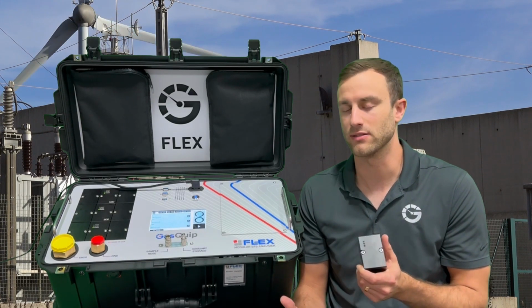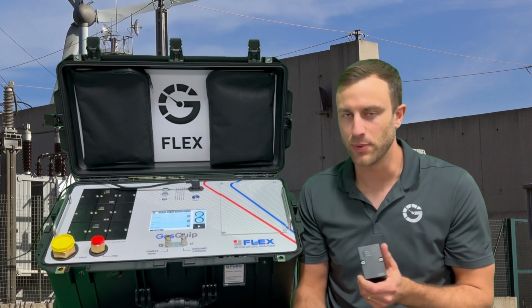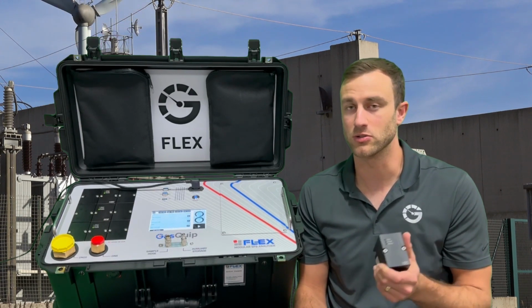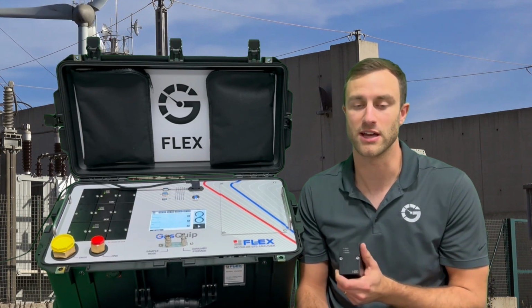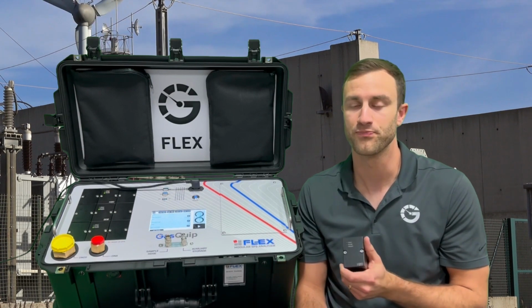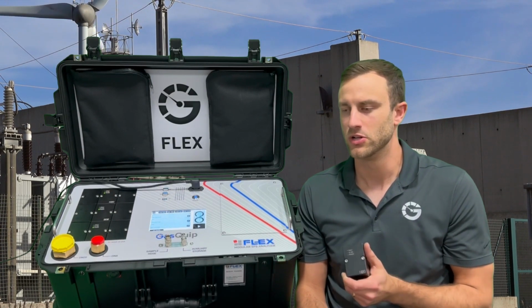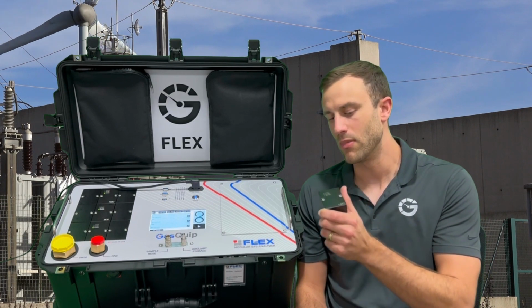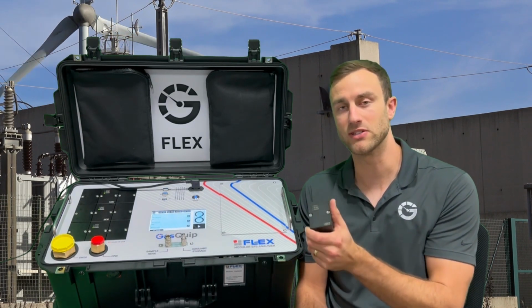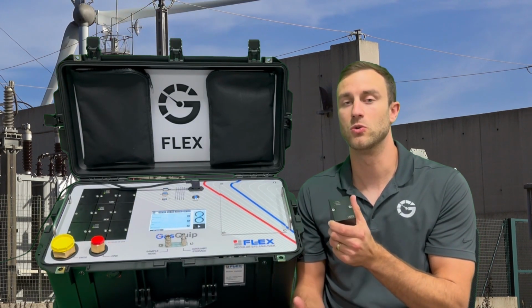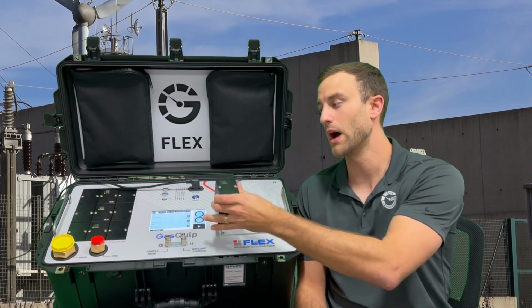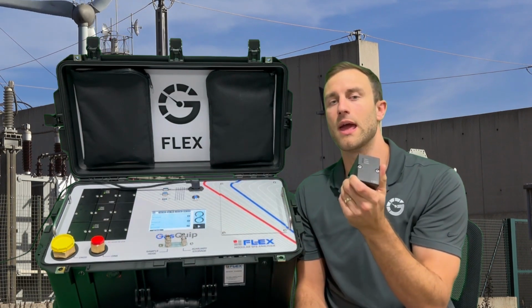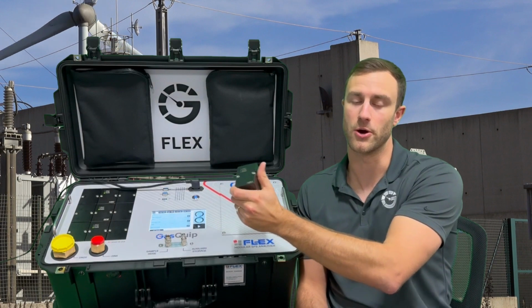And not only that, they're dealing with the shipping logistics and damage that goes along with shipping UPS or FedEx to get those devices to and from the manufacturer. So we went with a modular sensor that just needs to be replaced whenever the calibration is due for that particular sensor. So you pop out the old sensor and pop in the new sensor and you're good to go.